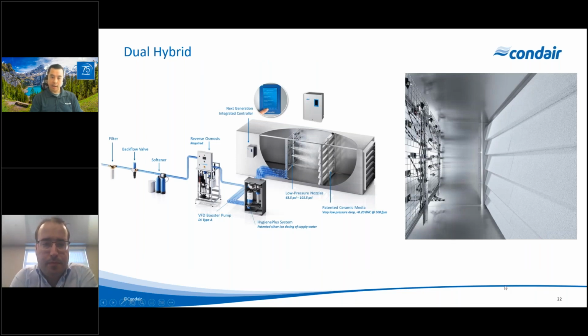The other technology that we'll look at here that is effectively a combination of those two previous products is what we call the dual or the hybrid system. So this is a low pressure atomizing nozzle system with an evaporative media downstream. So the big differences here are we are atomizing the water at about 100 to 150 PSI compared to about 1000 PSI with the high pressure system.